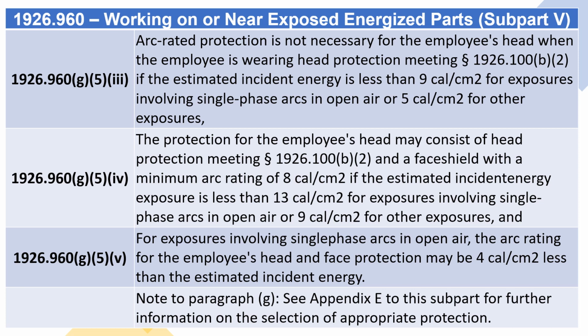The protection for the employee's head may consist of head protection meeting section 1926.100(b)(2) and a face shield with a minimum arc rating of 8 calories per square centimeter if the estimated incident energy exposure is less than 13 calories per square centimeter for exposures involving single-phase arcs in open air or 9 calories per square centimeter for other exposures, and for exposures involving single-phase arcs in open air, the arc rating for the employee's head and face protection may be 4 calories per square centimeter less than the estimated incident energy. Note to paragraph (g)(5): See Appendix E to this subpart for further information on the selection of appropriate protection.